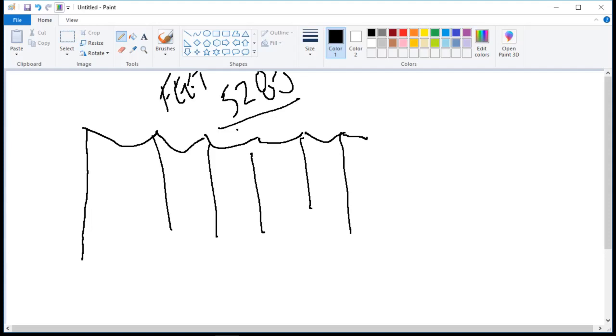You're going to reconductor all at once. You're not going to come in, pull 500 feet and put a splice in it, then pull another 1,000 feet and splice again. That's not how they operate. They want to pull the full 5,280 feet when you pull in the new conductor without any splices, because as soon as you introduce a splice you get high resistance and poor conductivity. So you want to know this number.